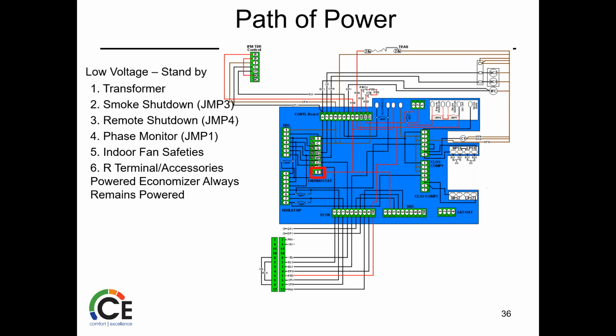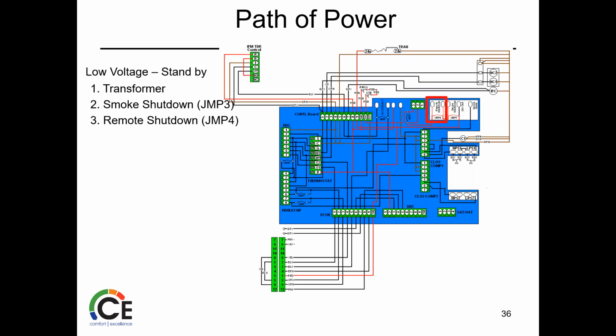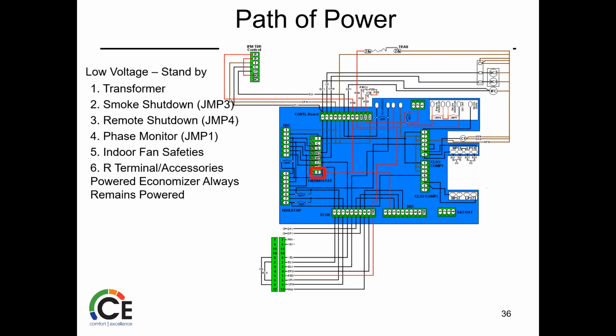So if the fan switch is open, or if remote shutdown is open, or a smoke shutdown opens for some reason, there's an issue, you're never going to get power here. And I know it's one of those things that the first thing everybody wants to test is they want to check R and C, and I get the phone calls, hey, I'm on a rooftop, I don't have power at R and C, but we've never checked the path that goes through. So start to look at that and follow that. You've got to see it here, and you've got to work its whole way, because that's the last thing it powers.